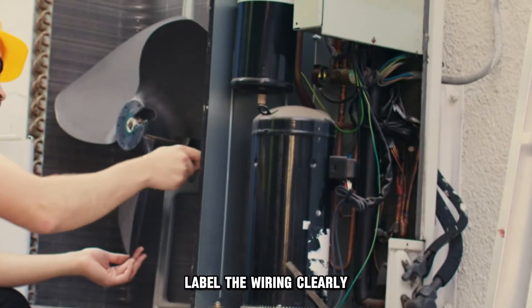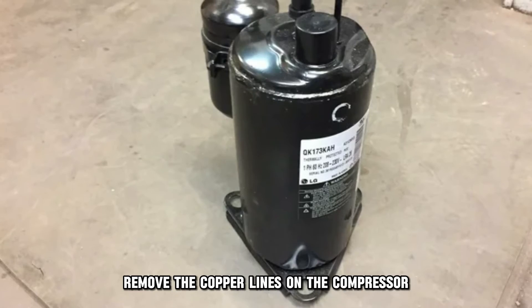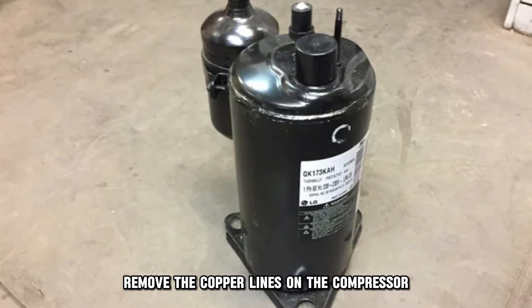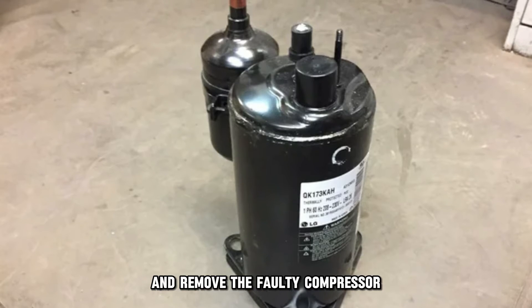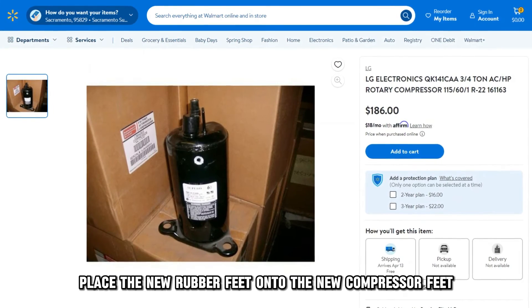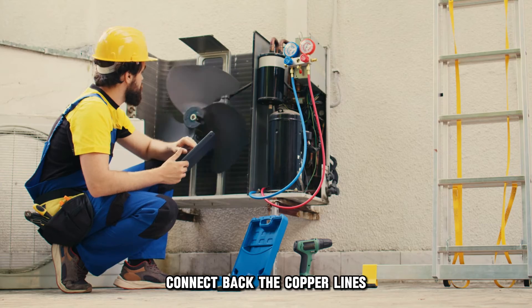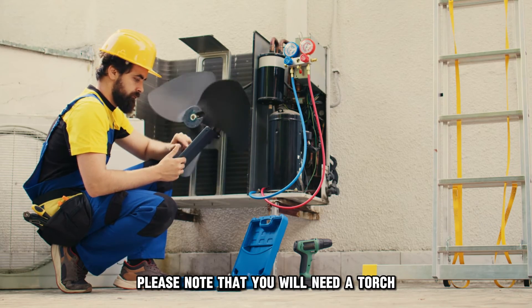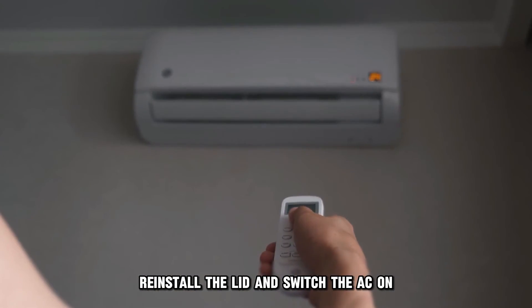Label the wiring clearly and remove the bolts holding the compressor feet. Remove the copper lines on the compressor and remove the faulty compressor. Place the new rubber feet onto the new compressor feet. Install and tighten the new compressor into place. Connect back the copper lines — please note that you will need a torch. Reinstall the wiring, then reinstall the lid and switch the AC on.